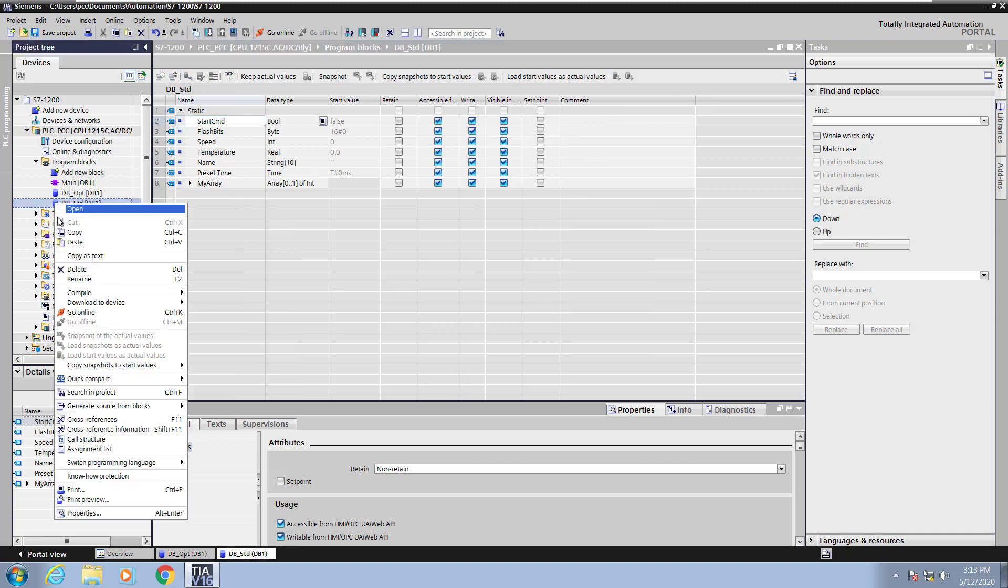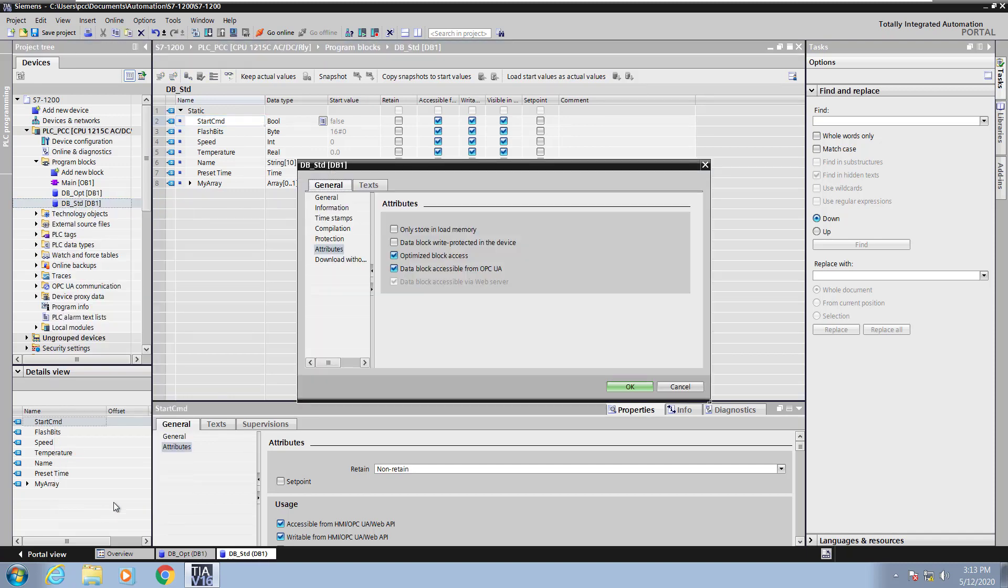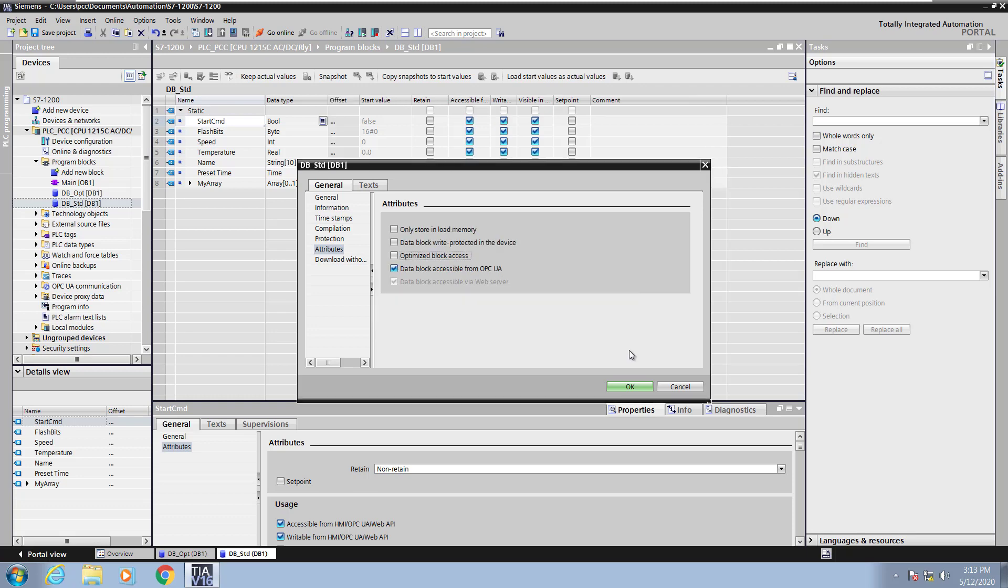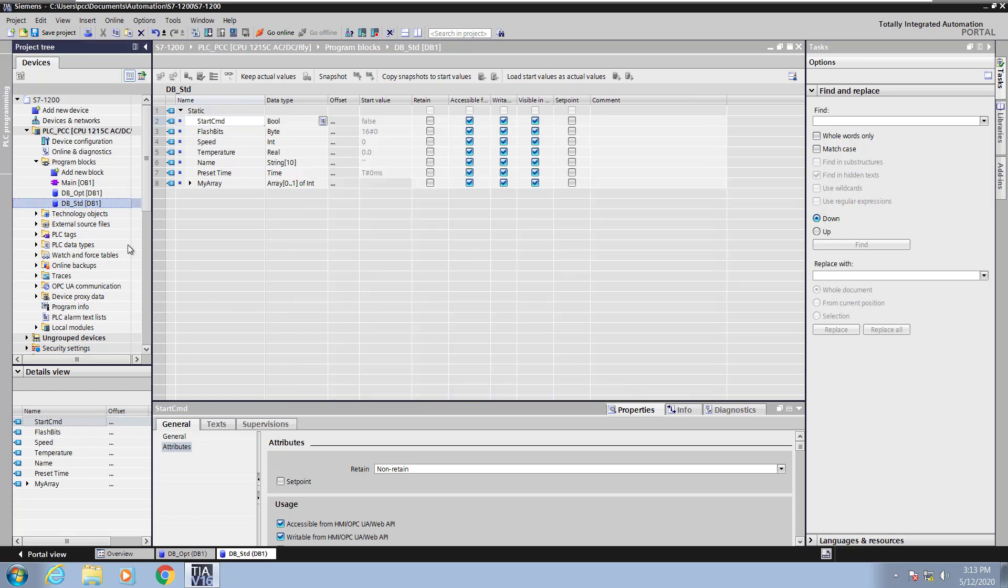Next I'm going to right click on the data block and select the properties for the block. There's an attribute that is called Optimize block access. So I'm going to uncheck that and this is going to change it from optimized access to standard access. Optimize is name only access. When I do standard access now you'll see that there's actually going to be an offset column in the data block.